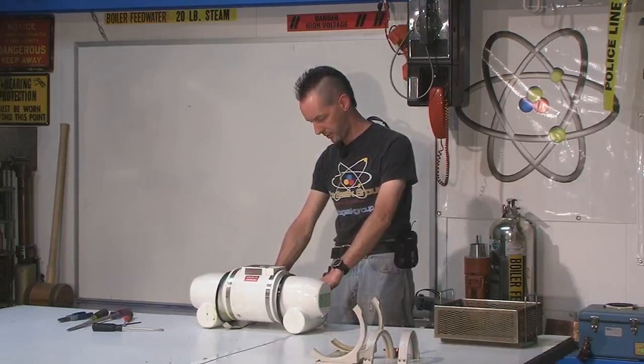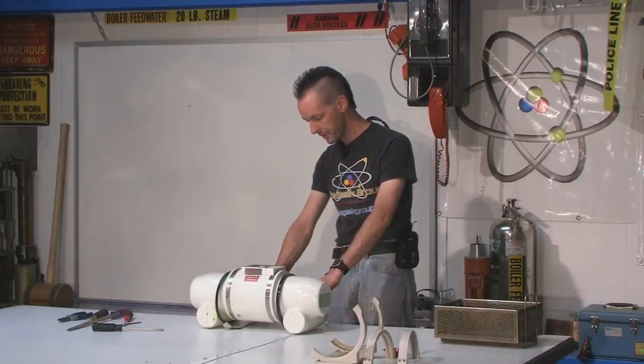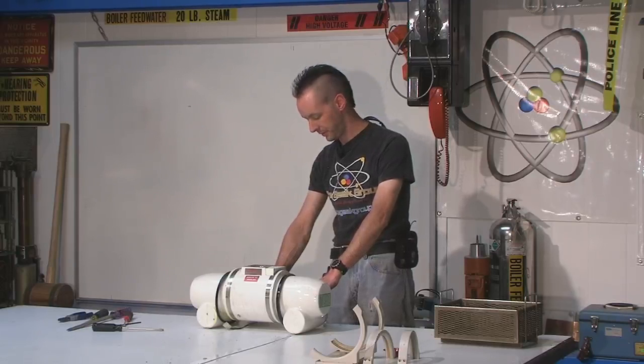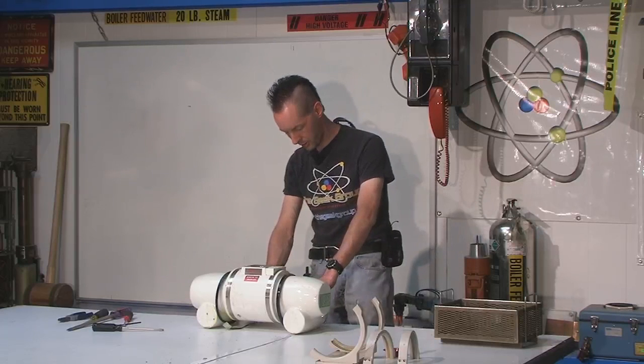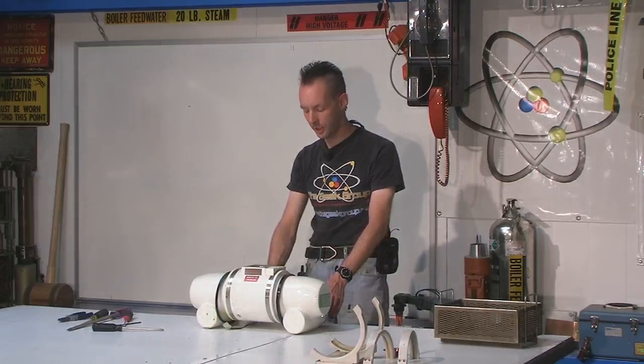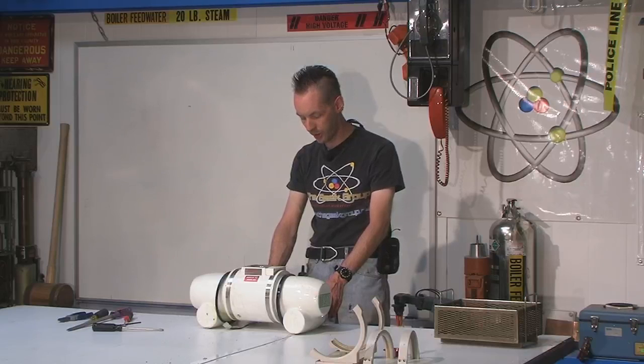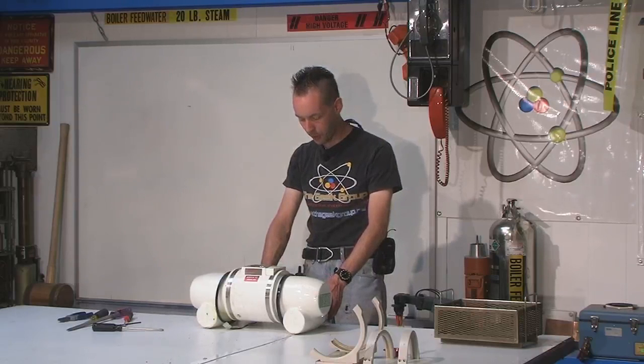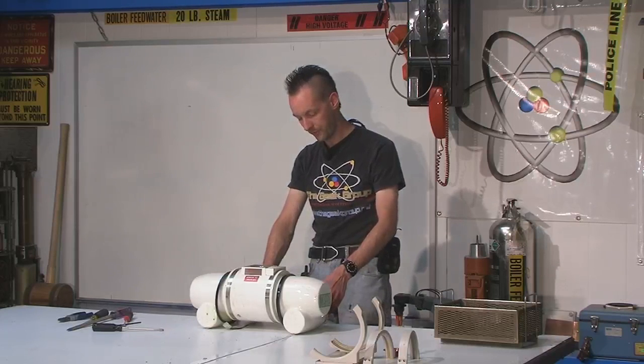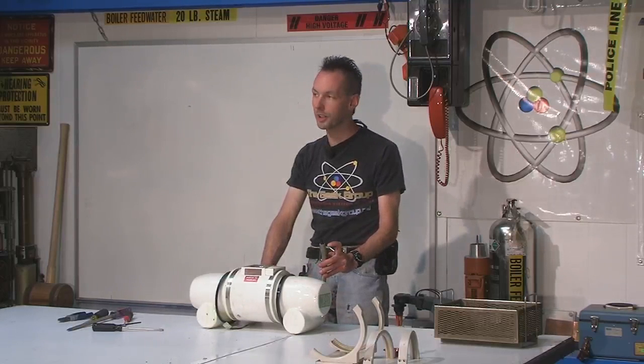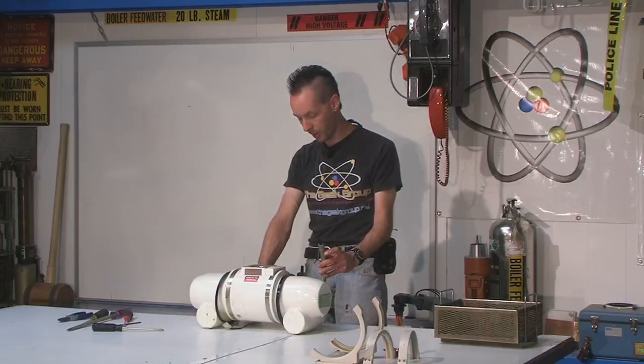It's just transformer oil. More mineral oil. More mineral oil. Yeah. There's no PCB hazard with this. Yeah. The same rules when dealing with this kind of oil apply as we're dealing with the medical-grade transformer oil. PCBs are pretty rare. General Electric has never used PCBs in any of its medical-grade transformers. I can hear this bubbling on this side. So I'm just holding one up and one down. And it's pouring out of the other one like crazy.